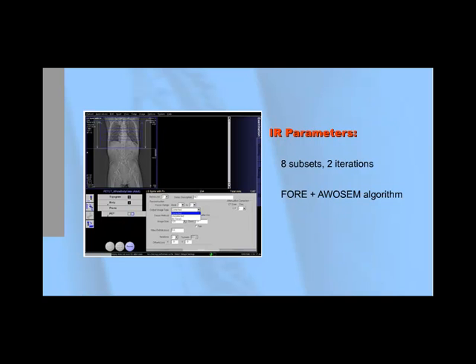The typical whole body iterative reconstruction parameters are generally as follows: 8 subsets, 2 iterations, FORE and AWOSEM algorithm, and 6mm Gaussian smooth filtering.